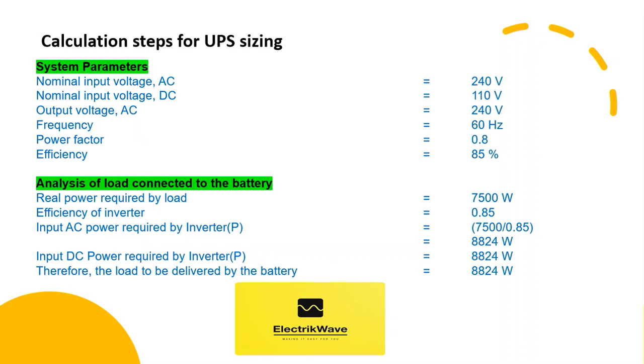System parameters considered: Nominal Input Voltage AC equals 240V, Nominal Input Voltage DC equals 110V, Output Voltage AC equals 240V, Frequency equals 60Hz, Power Factor equals 0.8, Efficiency equals 85%. For analysis of load connected to the battery: real power required by load equals 7500W, efficiency of inverter equals 0.85, input AC power required by inverter equals 8824W, input DC power required by inverter equals 8824W. Therefore, the load to be delivered by the battery equals 8824W.